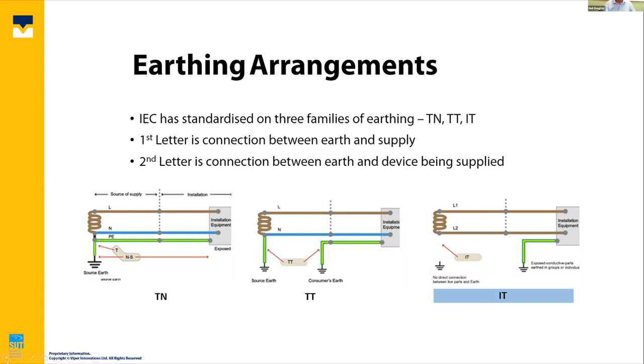What is more common in the UK utility supply? So what you will see within your house is the supply is connected to earth, and at the far end, the consumer is connected to earth at the neutral point. Hence, we have this TN configuration. So this is typically the configuration you have in your domestic house. And this is typically the configuration you have in most industrial applications. So if you go onto a building site, you see builders there with their little yellow boxes, transformers. Those boxes are converting a TN supply into an IT system.